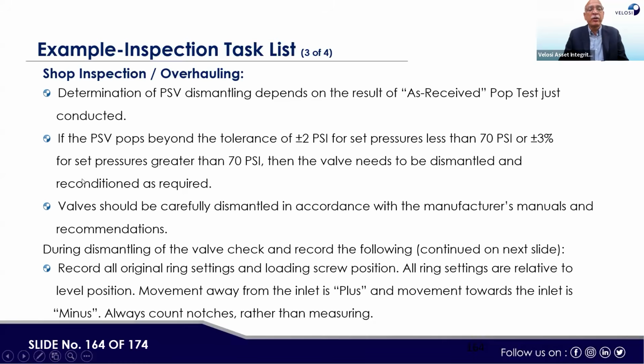Then shop inspection overhauling. When we are doing shop inspection overhauling for the PSV, these are general guidelines. Determination of PSV dismantling depends upon the result of the as received pop test just conducted. If the PSV pops beyond the tolerance of plus or minus 2 PSI of set pressure for less than 70 PSI, or 3% of the set pressure for greater than 70 PSI, then the valve needs to be dismantled and reconditioned as required. The valve should be carefully dismantled in accordance with the manufacturer manual and recommendation. During dismantling of the valve, check and record the following, continued on the next slide.